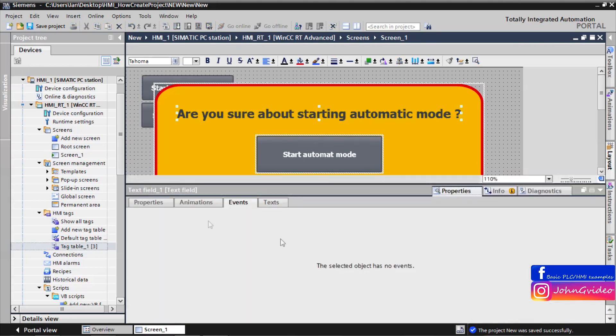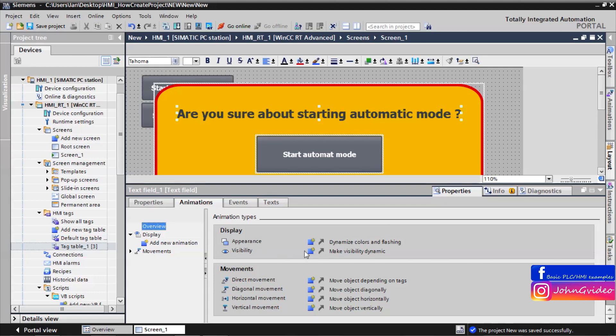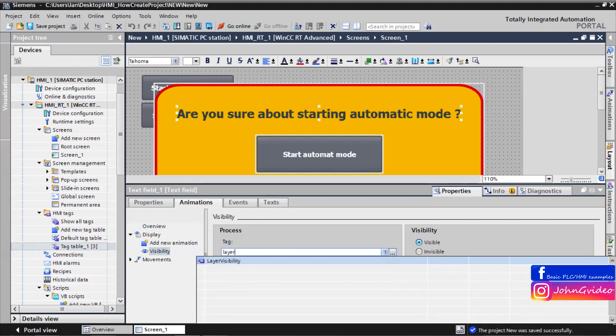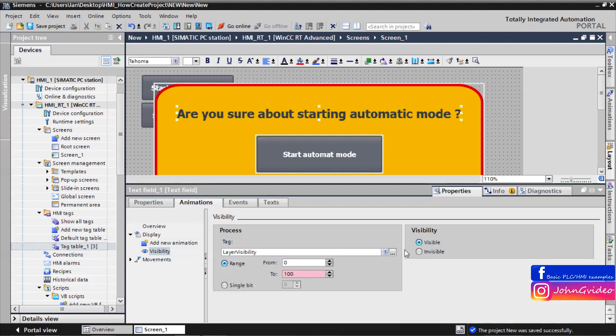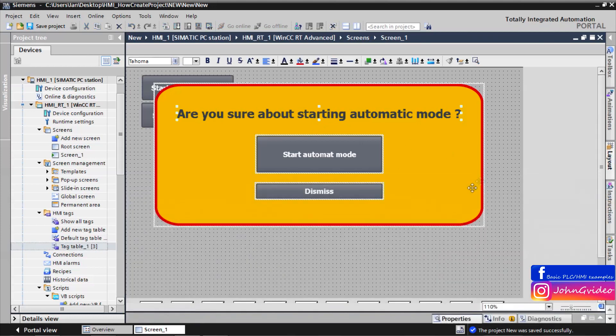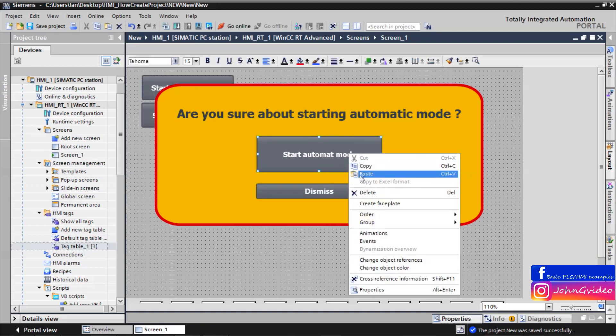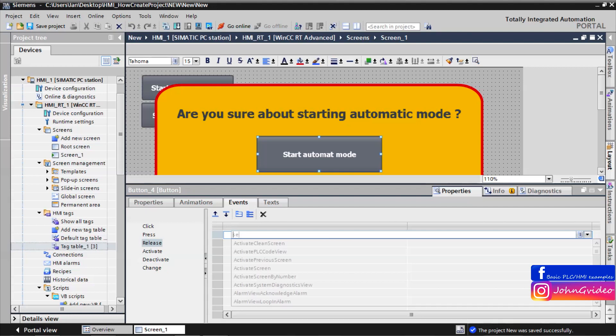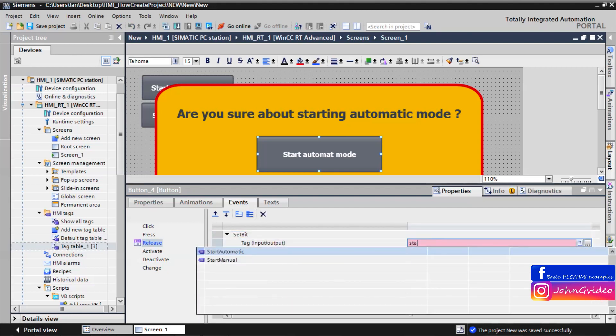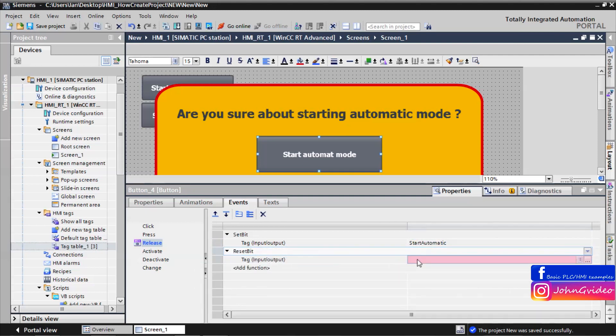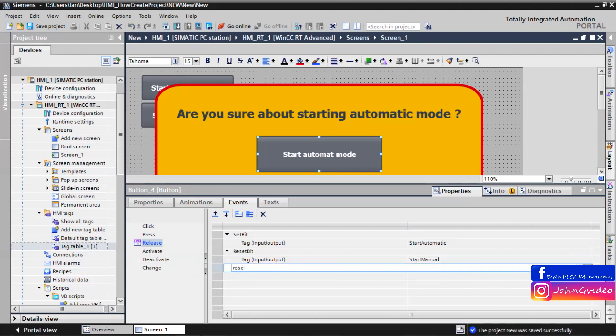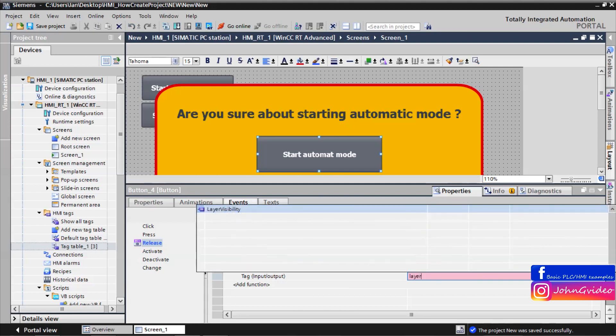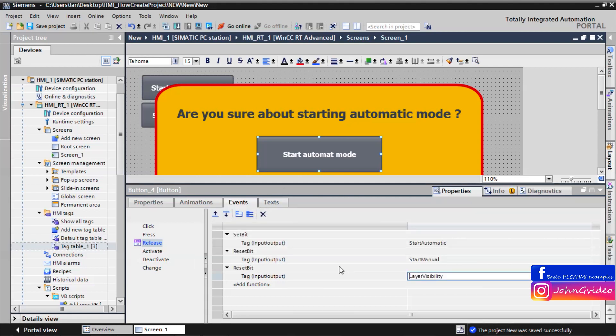We check all the objects of the confirmation window. We go to the animation, and in the visibility, as the process tag we use 'layer_visibility'. When 'layer_visibility' is true — for us, number 1 — then the confirmation window objects are visible. Then if we release the 'Start Automatic Mode' button inside the confirmation window, we set bit 'start_automatic' and reset bit 'start_manual', and we also reset bit 'layer_visibility' to close the confirmation window after the action.